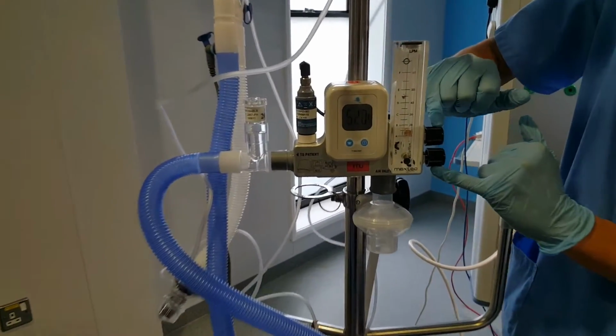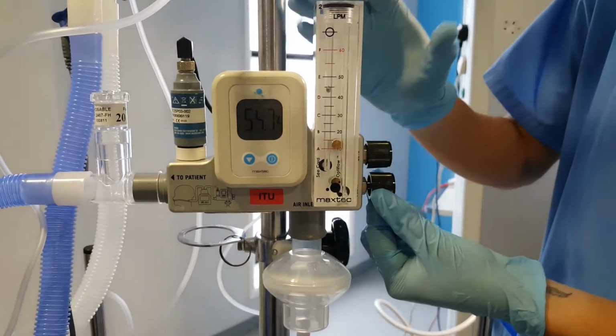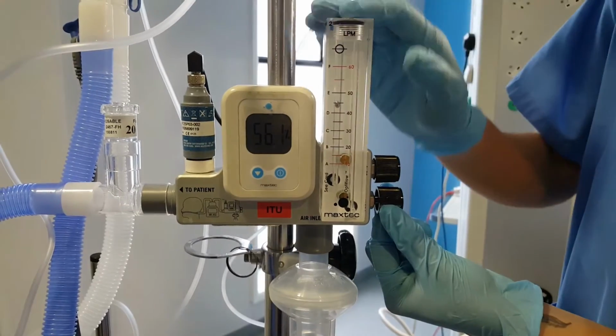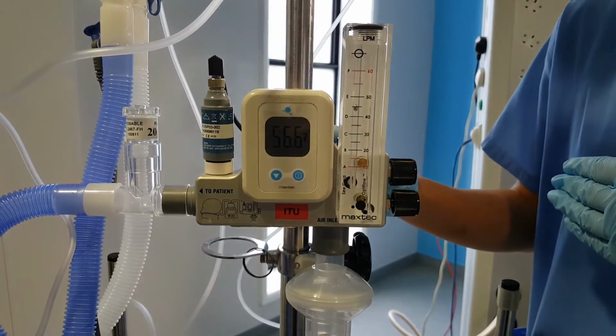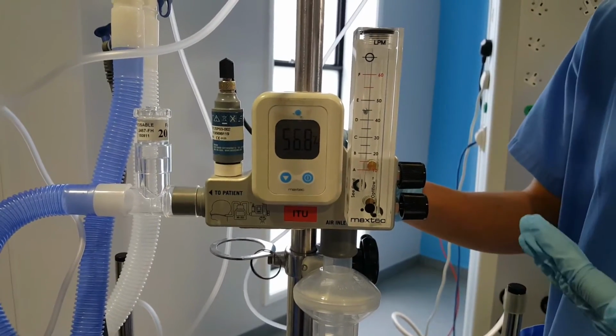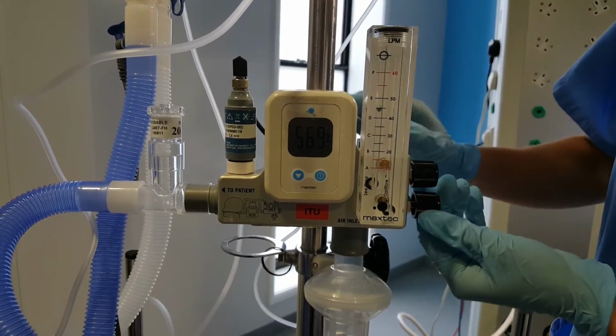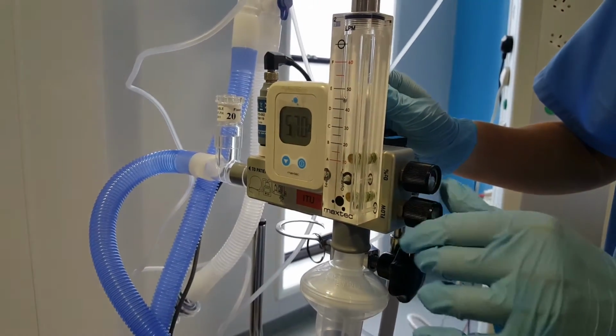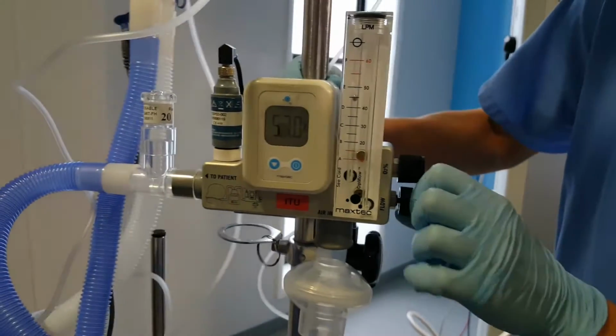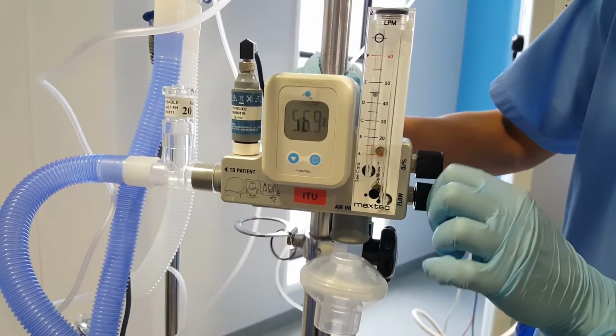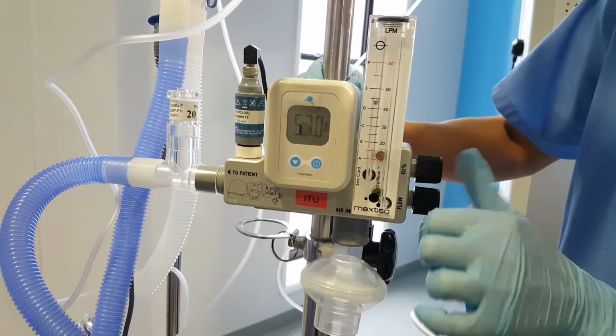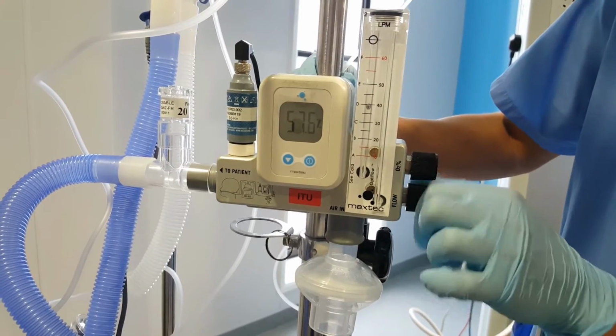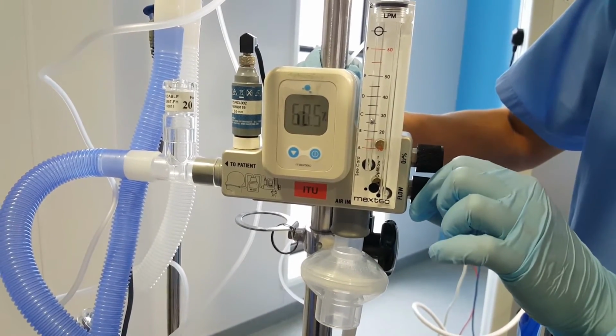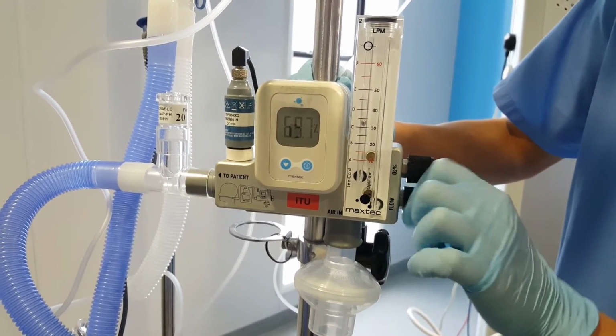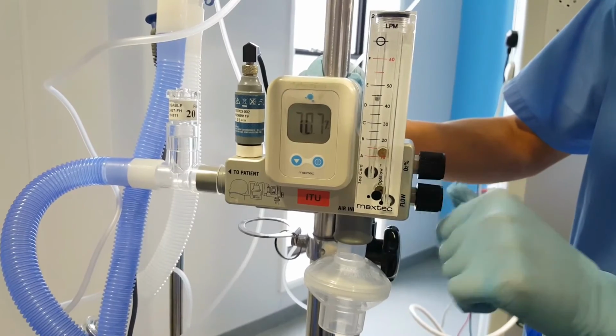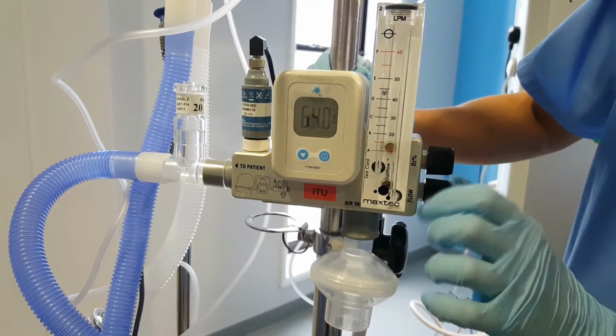There are two knobs on the side of the oxygen percentage monitor, one of which is a flow, which provides the amount of pressure and flow at which you're providing your oxygen, and that can go up to 60. By changing that, you just turn the flow meter, and you will see the little silver ball inside go either up or down. So I am bringing it down at the moment, and I want to bring it down to 20. So your flow will depend on your patient's comfort as well, but when you're giving CPAP, we would recommend 40. So it'll hover just around here.